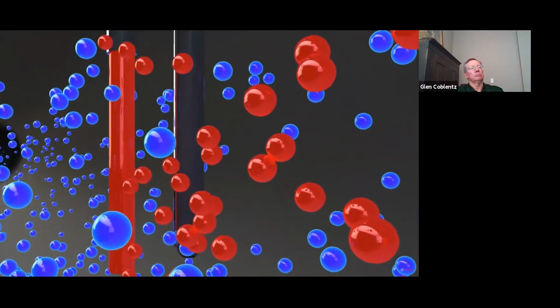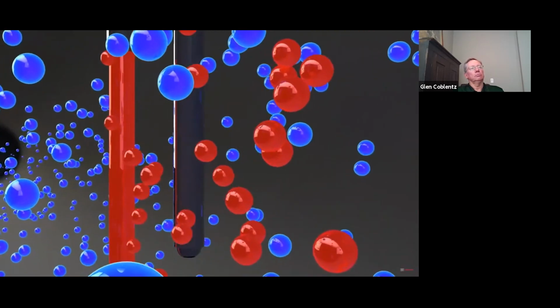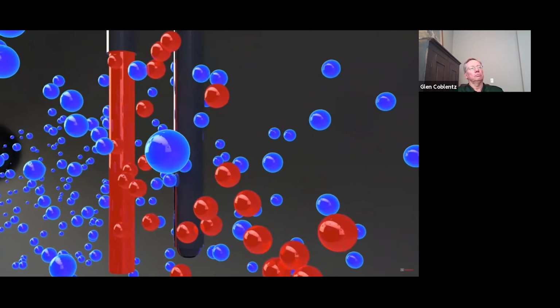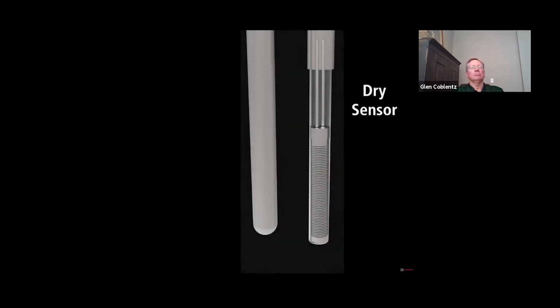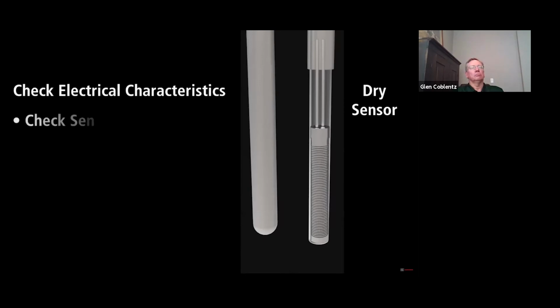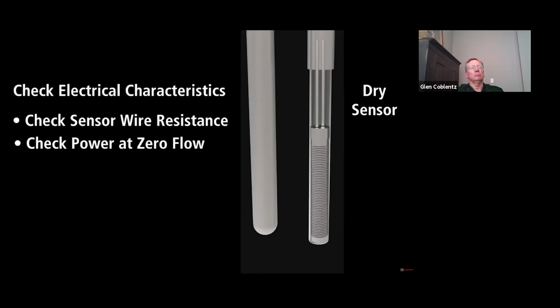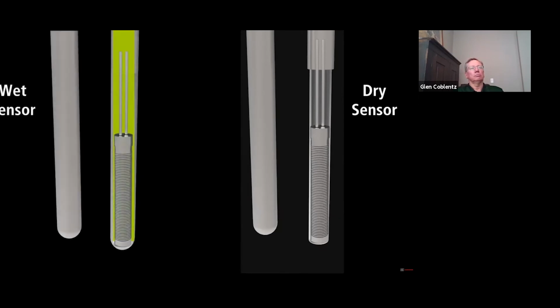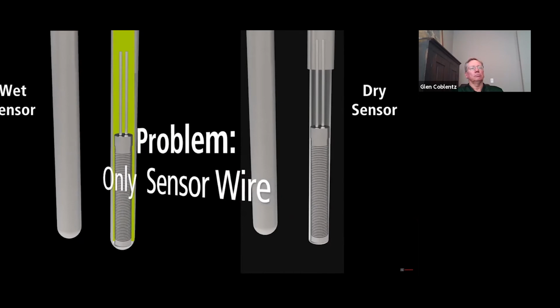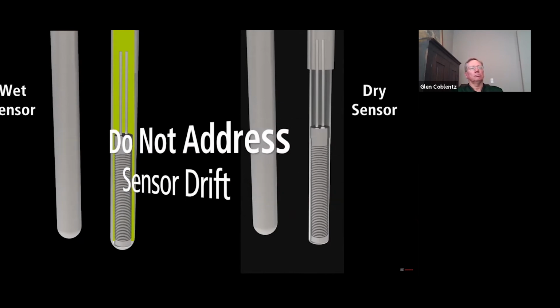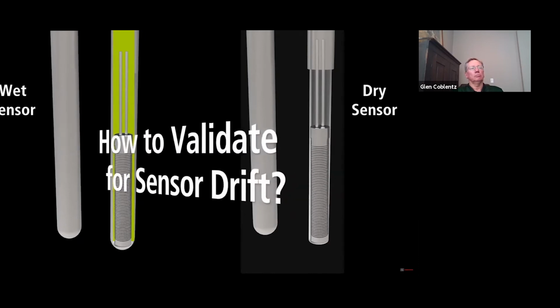There is a lot of smoke and mirrors by thermal manufacturers about in situ calibration. All thermal manufacturers have generally the same method of in situ calibration validation to confirm the original factory calibration while checking for drift and assuring accuracy. The basic process makes use of the electrical characteristics of the sensor, either by checking that the electrical resistance of the velocity sensor's platinum resistance temperature detector wire has not changed over time, or by assuring that the power sent to the velocity sensor at zero flow is the same as when it was first calibrated at the factory. The problem with both methods is that they only measure the characteristics of the internal sensor windings and do not address sensor drift.